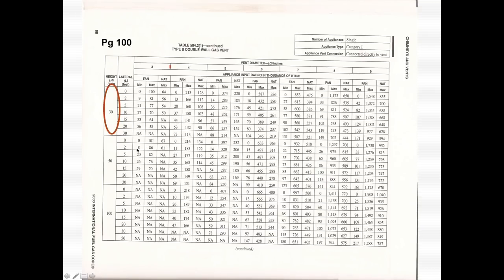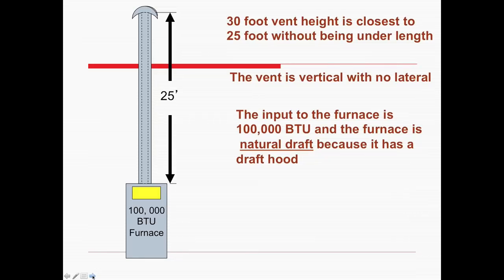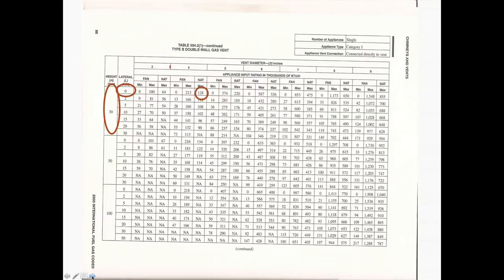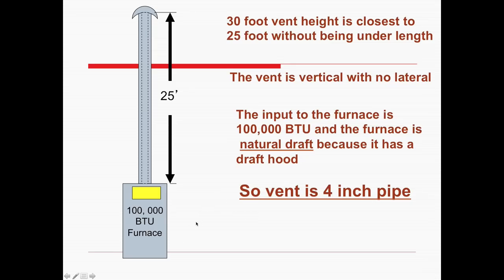Here's the page. We have a 30-foot height, no lateral, so the lateral is zero. The input of the furnace is 100,000 BTUs and the furnace is natural draft because it has a draft hood. Going across to find the one that will work — we have fan minimum and maximum, and natural. On three-inch pipe it won't work, it's too small at 64,000. Going to four-inch we have 128,000. So we end up with a four-inch vent pipe.